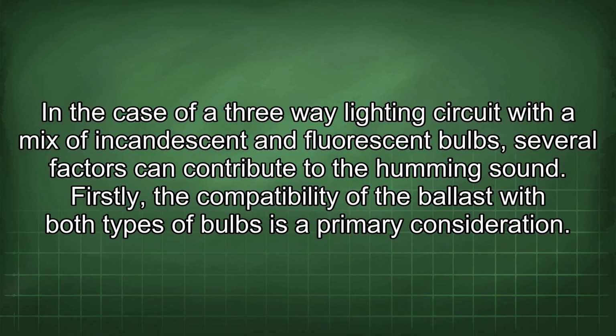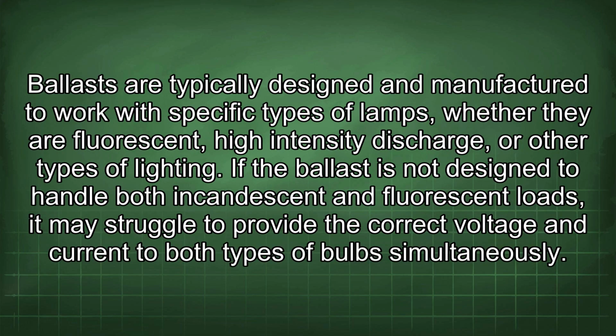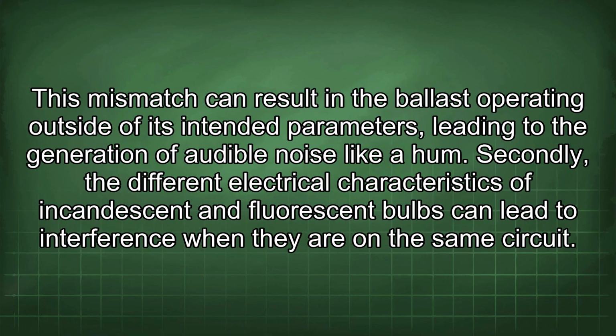In the case of a three-way lighting circuit with a mix of incandescent and fluorescent bulbs, several factors can contribute to the humming sound. Firstly, the compatibility of the ballast with both types of bulbs is a primary consideration. Ballasts are typically designed and manufactured to work with specific types of lamps, whether they are fluorescent, high-intensity discharge, or other types of lighting. If the ballast is not designed to handle both incandescent and fluorescent loads, it may struggle to provide the correct voltage and current to both types of bulbs simultaneously.